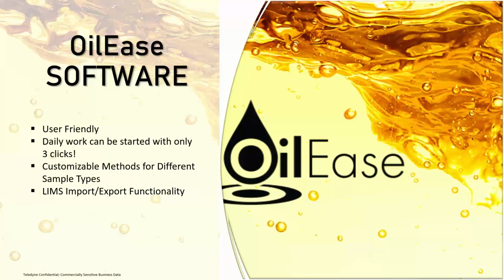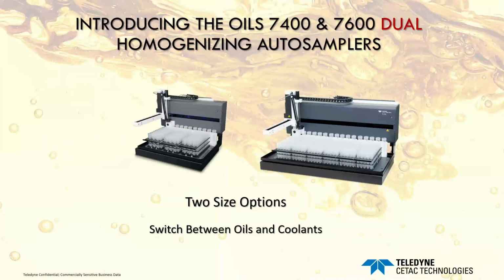All right, and I alluded to these before, but we have the samples diluted, so we're ready to send them to the ICP, so now we need an auto sampler. The Oil 7400 and the Oil 7600 are auto samplers purpose-built to serve oil labs. They are identical in capabilities to each other, with the only difference being the number of racks they can hold. The Oil 7400 can hold 4 60-position racks, while the Oil 7600 can hold 6 of the same rack. And while they have oil in their name, they can also handle coolants. Not only that, but we've built them to be able to easily switch between those two sample types.